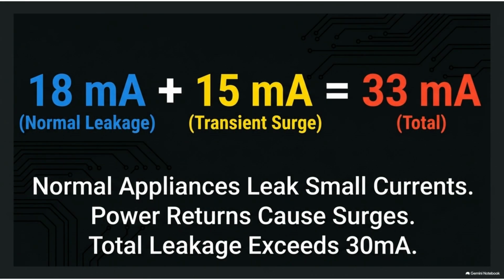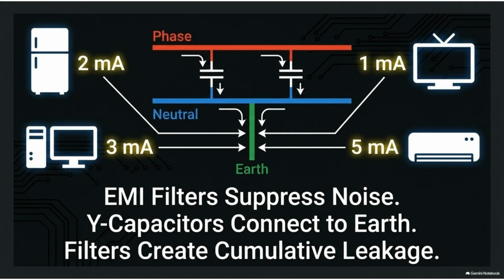When power returns, normal appliances may experience transient surges. If this surge combines with your appliance's existing normal leakage and exceeds 30 milliamps, the RCCB will trip as a safety measure. Many electronic devices use EMI filters with Y-capacitors that connect to earth to suppress noise. These components can create a cumulative leakage current, which contributes to the overall load on your RCCB.